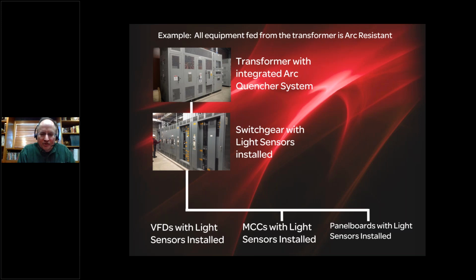So the arc quencher does have a maximum withstand rating, which is 100 kA, 100,000 amps, for the low voltage quencher. For the medium voltage quencher, it's 50,000 amps. That's the maximum fault current environment into which it may be applied. So when applied within that withstand rating, when properly applied and installed, we absolutely provide documentation and a guarantee that the downstream equipment will be less than 1.2 calories per centimeter squared, and therefore arc resistant. Great question.